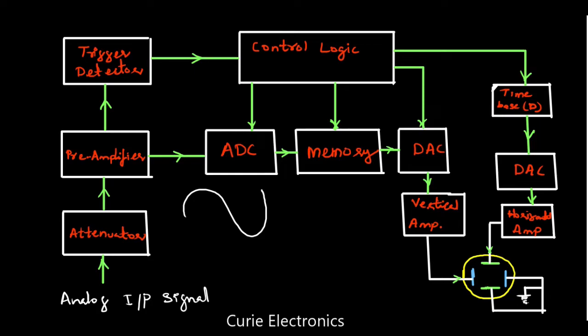From the control logic, we also need to generate the sweep. The control logic triggers the sweep generator — that is the time base — which gives a sawtooth wave. This is a digitally controlled sawtooth, and the digital values are converted to analog via a DAC, producing an analog sweep waveform — a ramp. That ramp signal drives the horizontal amplifier, which then drives the horizontal plate. The cathode ray tube then reproduces the waveform, the same working principle we saw in the previous video.